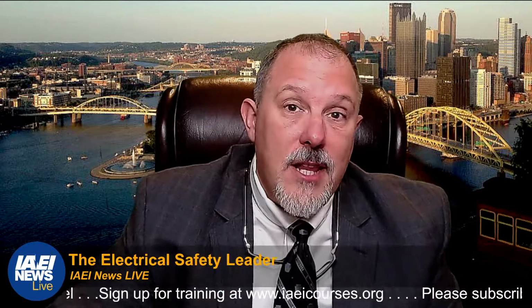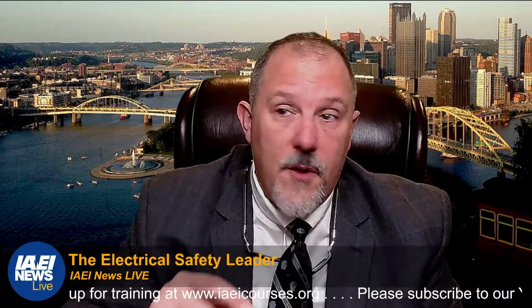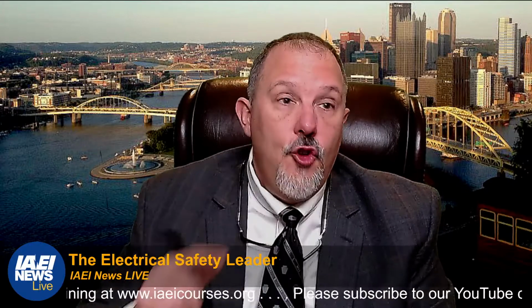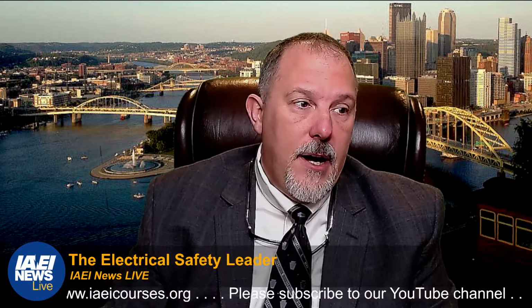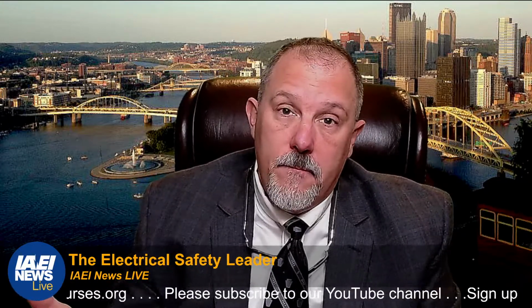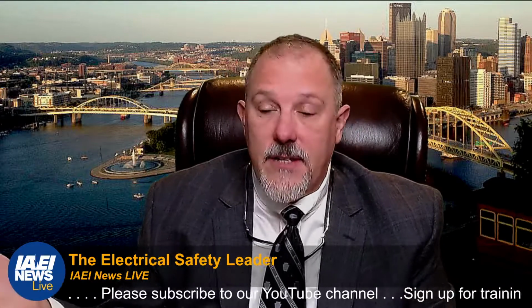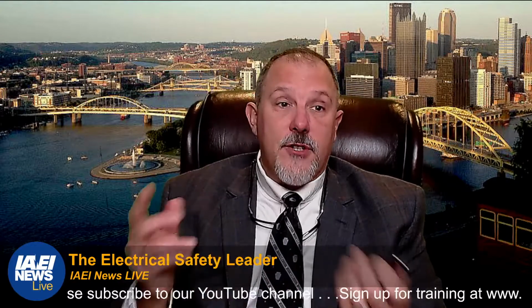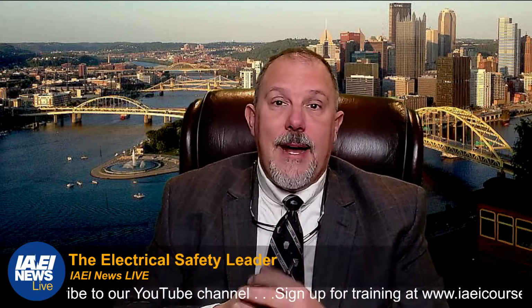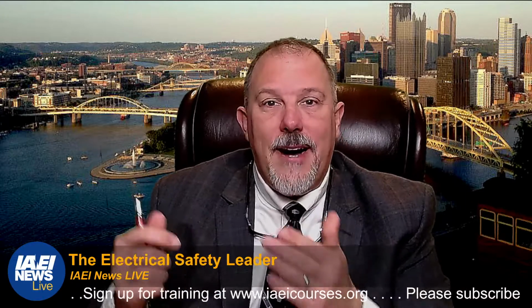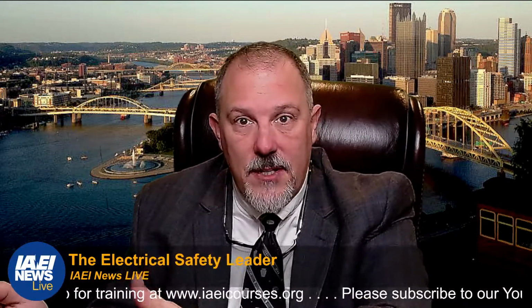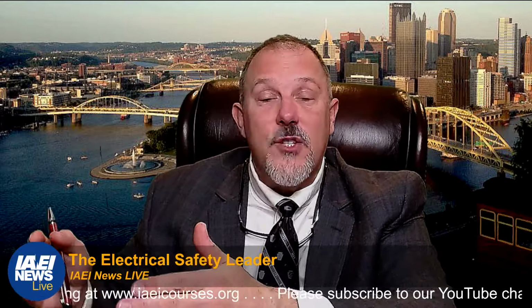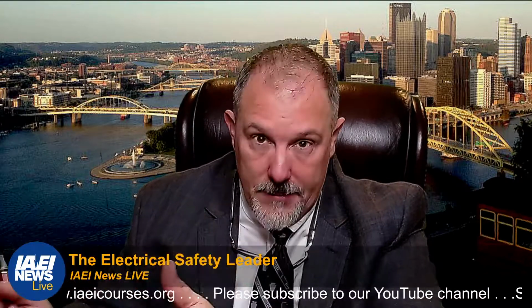You should look at their practices. You may not agree with their thermography process. You may not agree with how they test their circuit breakers. You may find out that, yeah, they have a circuit breaker test plan, and their circuit breaker test plan is look at the outside and make sure it looks clean. And that's all they do, right? Because until now, we didn't have a document that said this is what you shall do as a minimum.